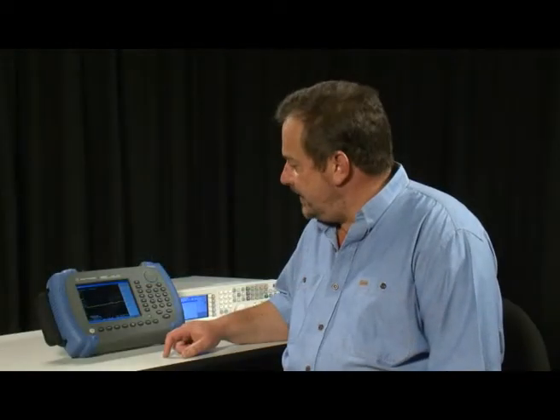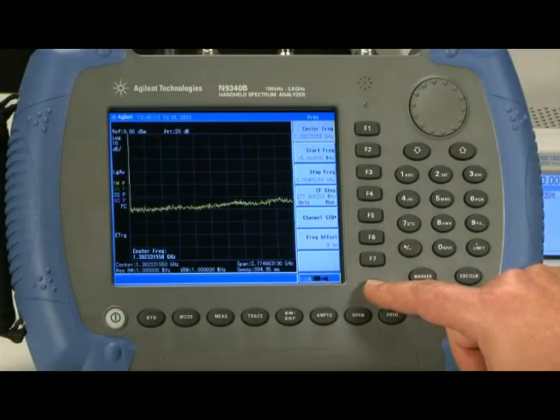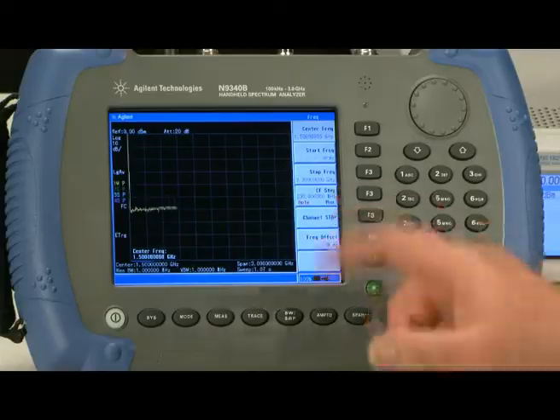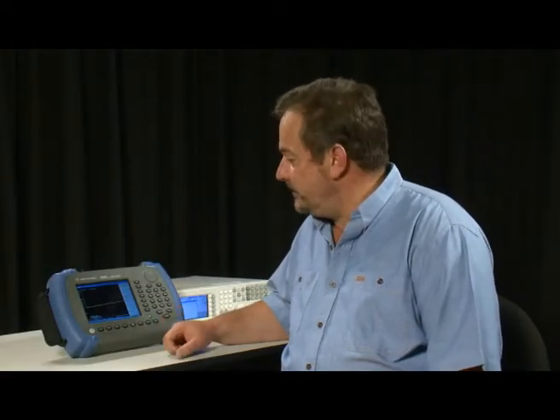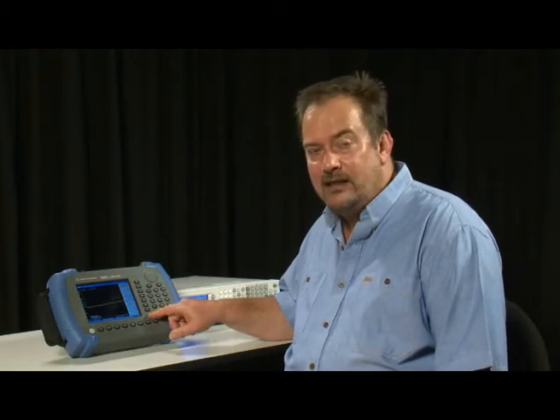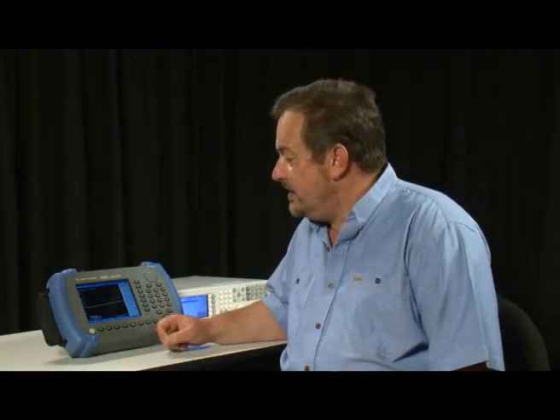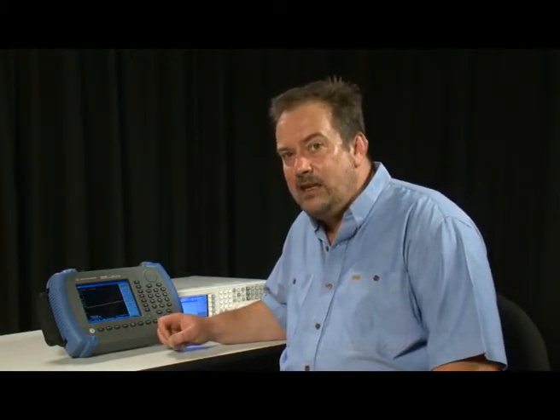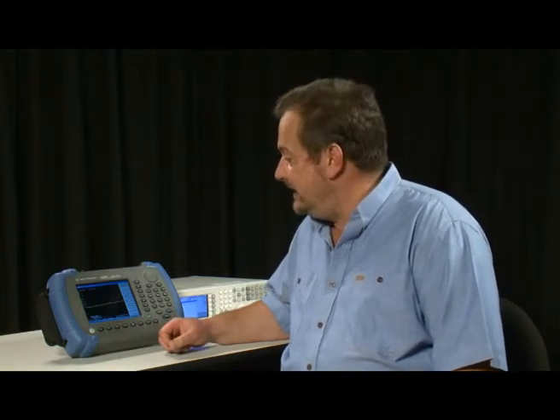And probably the most useful button on the entire instrument is the green preset button. Pressing this resets the instrument and puts it back to its factory default state. It is highly recommended that you always press that green button before starting a new measurement to make sure that any strange settings that a previous user may have set up within the instrument have been cleared.